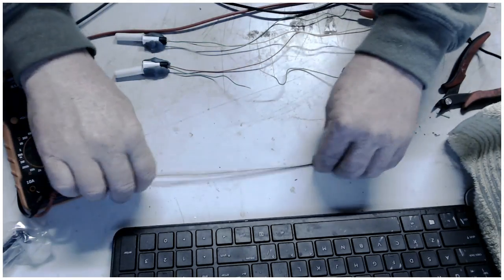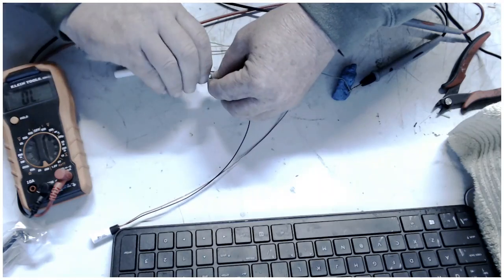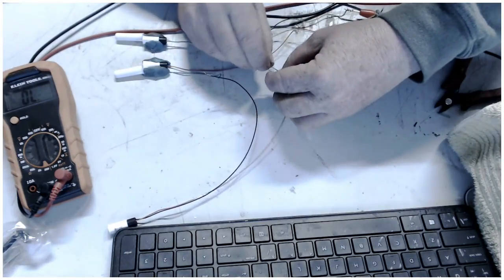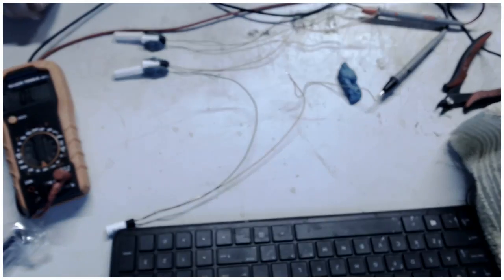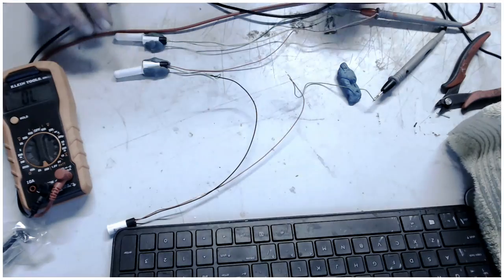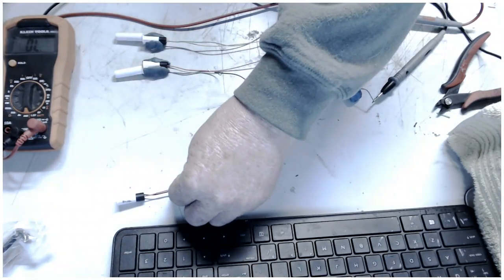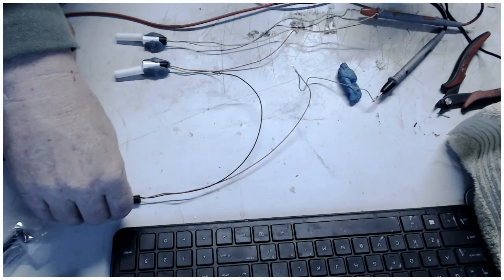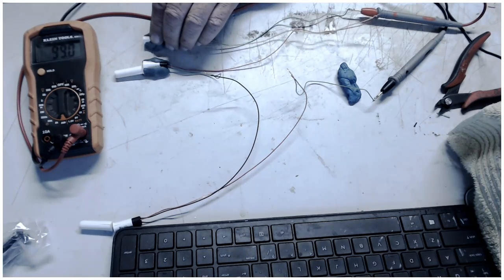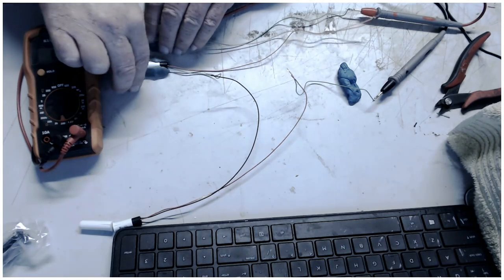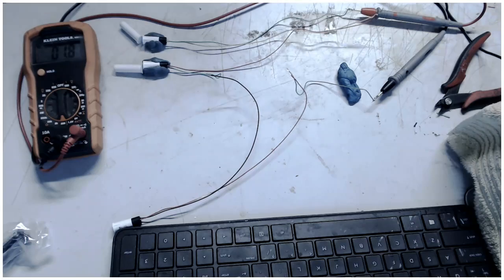What you do now with the new contact you're trying to put in, you take one leg of it, wire it in here, take the other leg, pop it in there. But you say, wait a minute, I got it in there now, but it's still open on my meter. What you have to do is you take another magnet, you put it on that third contact, and if you notice, now it's closed. So if I open this, open. I open this one, open. Open this one, open.